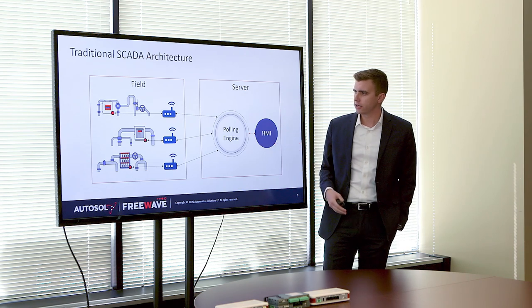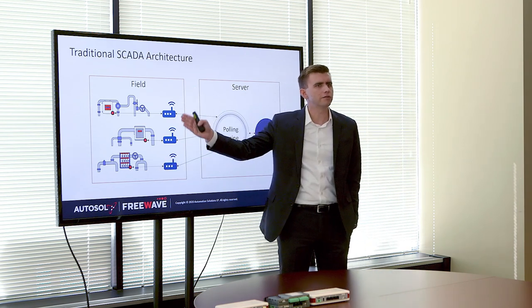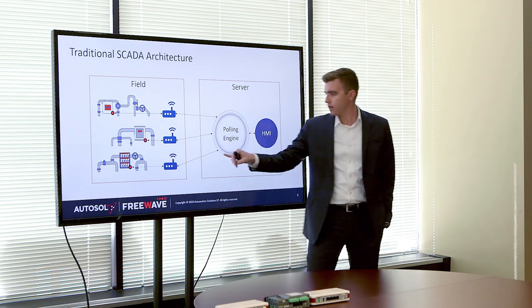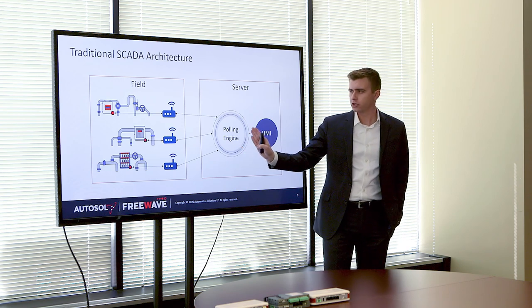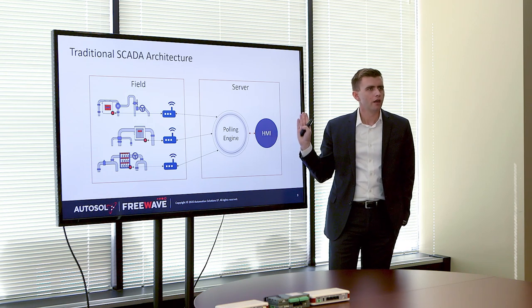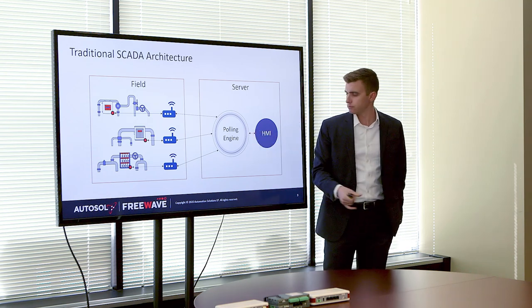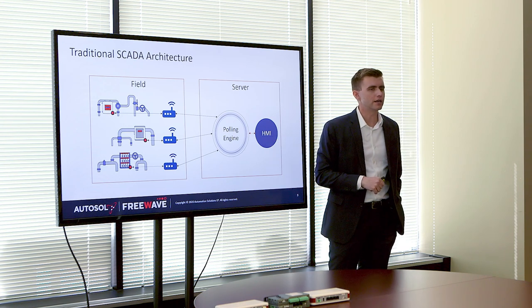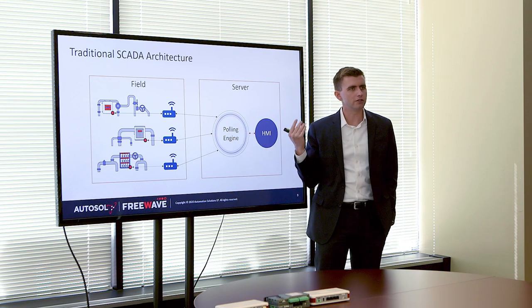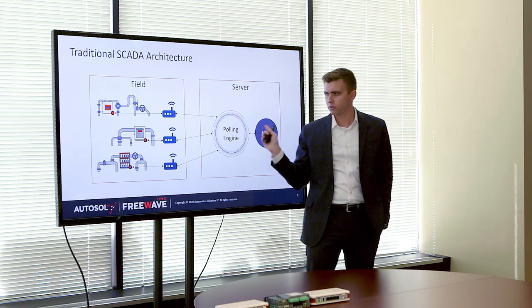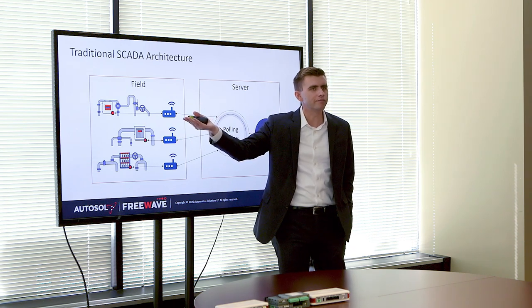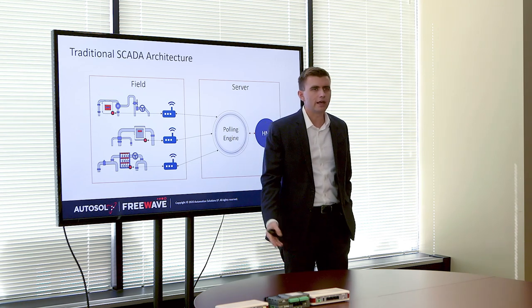In traditional SCADA architecture you have your end devices, some form of communication — radios, cell modems — and a polling engine such as ACM which talks native protocol to the end devices and converts that to OPC for an HMI. The structure is based on poll-response. An operator has a list of a thousand tags he wants in his HMI; he polls and gets the data from the end device. If only a hundred or two hundred of them changed, he's still going to send all one thousand tags up even if they haven't changed.